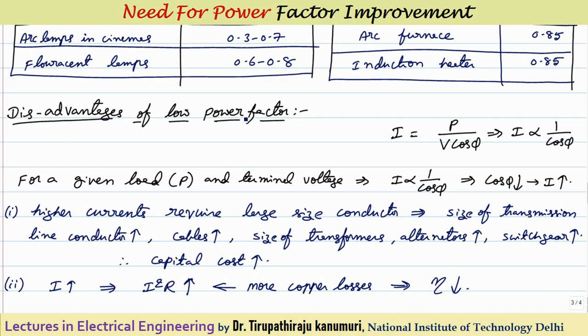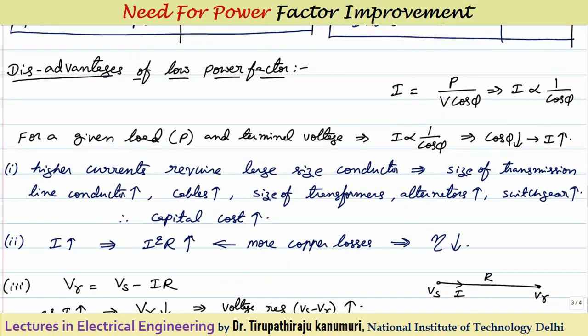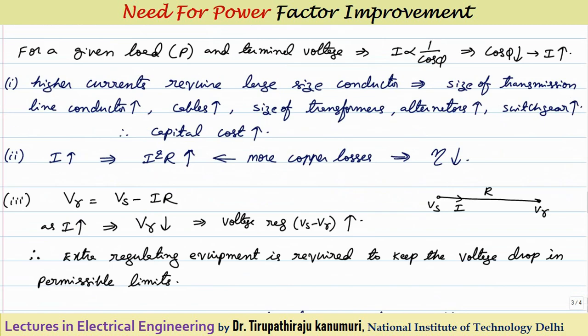What are the disadvantages of low power factor? Since most equipment operates at lagging or low power factor, and current I equals P divided by V·cos phi, for constant P and V, the current is inversely proportional to cos phi — so as cos phi decreases, the current drawn from the supply increases. When more current flows, the equipment must supply it, and starting from the transmission line, the conductor size increases. For cables, larger conductor size means larger cable size overall.